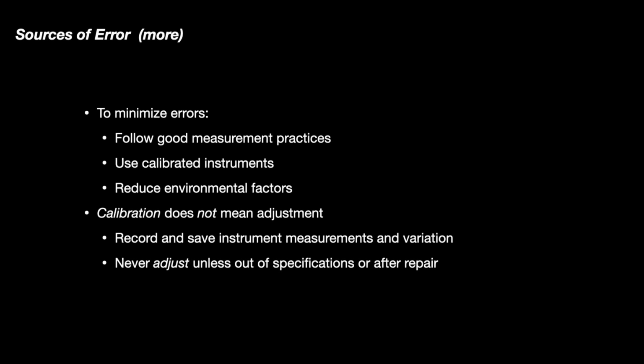Calibration is about keeping a history of the instrument's performance against a standard that has been established for that purpose. So what you really want to know is, if I've got a voltmeter and I measure it against a 10-volt source, and that 10-volt source is calibrated, what is it measuring today? What did it measure last week? What did it measure last month? About last year? And the history of the instrument with the calibration is what matters, because as long as the instrument is within the specifications set by the factory, it's good to go.